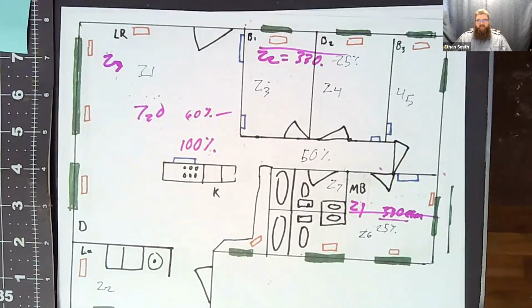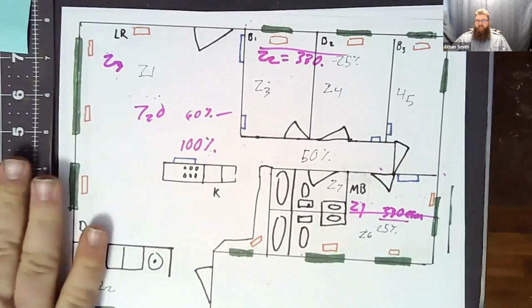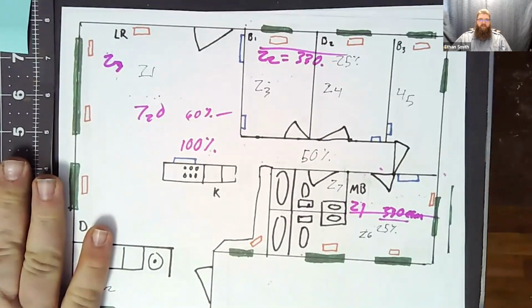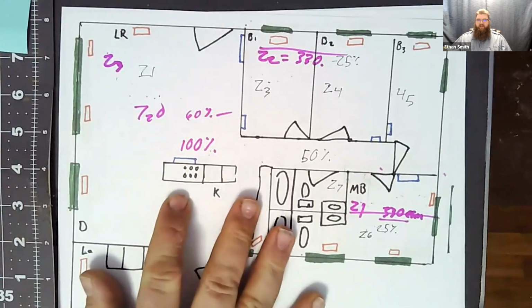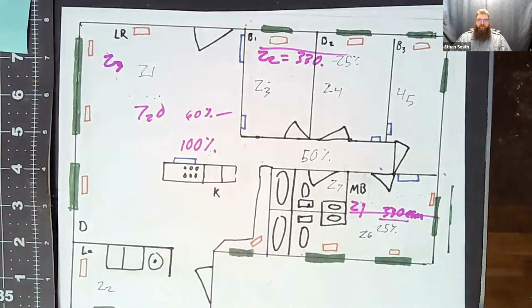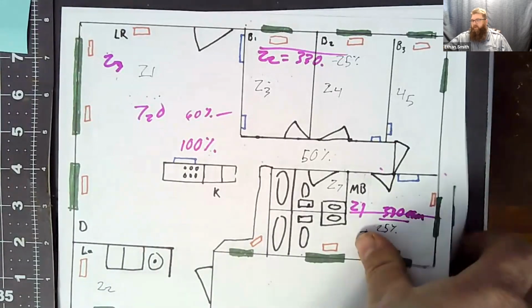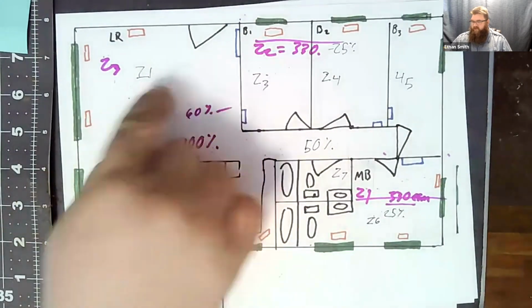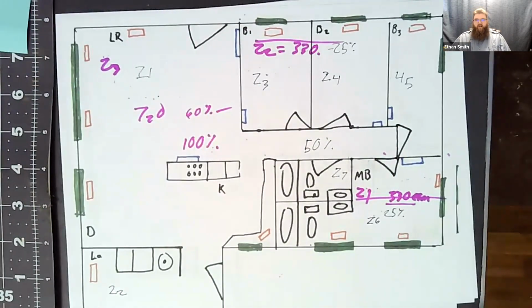Okay. So zoning can do a lot of good things for you guys. Integrated zoning with modulating capacity equipment can make zoning sing for you. Okay. But you got to do the homework, you got to make sure the ductwork's there. You got to make sure the return's there. You got to make sure you've got all of that segmented out properly. Otherwise, you start to have problems.